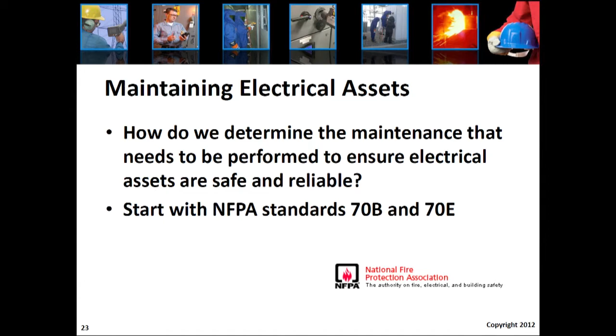NFPA 70 is the National Electric Code, and it details the installation parameters - how many conductors, what size, and how many go in a piece of conduit. It makes sure you're at least installed safely. 70B addresses the operation and maintenance of the equipment, and 70E covers how to do that maintenance safely. So using 70B alone, it doesn't really take into account how your equipment is operated.